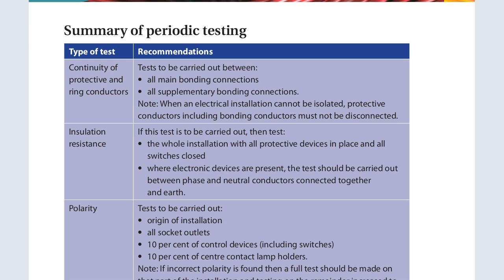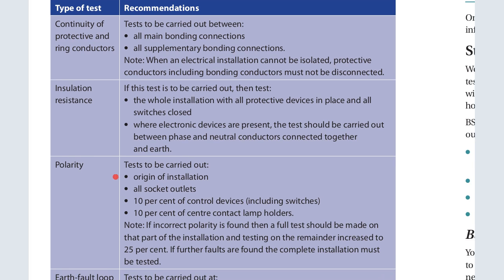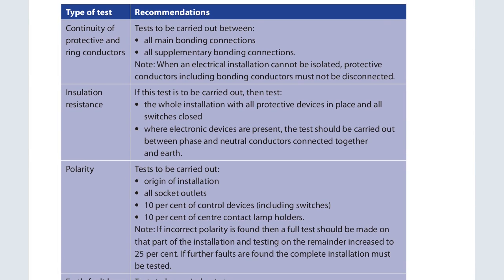Summary of the tests. We have now the continuity test, continuity of protective conductors. We said the types of tests that are carried out. Now the continuity test is the test to be carried out between all the main bondings and all the supplementary bondings, that is the equipotential bonding, to make sure that the earthing is properly installed. That is, all electrical installation cannot be isolated, the protective conductors, including bonding conductors, must not be disconnected. Another one is the insulation resistance.